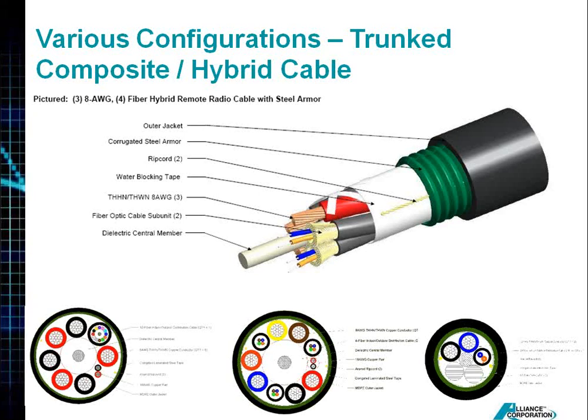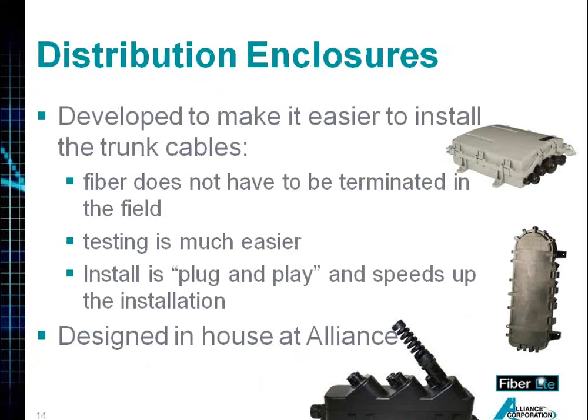Some of the configurations we've come up with over the years range from a 2-conductor, 8-gauge cable consisting of 8 fiber, all the way up to a 10-conductor 6-gauge cable with 48 fiber. Many of these configurations have what we call an armor or shielding, consisting of either corrugated steel armor, copper tape, and sometimes a braided shield. They all consist of water blocking tape, and they all include a strength member in the units as well.